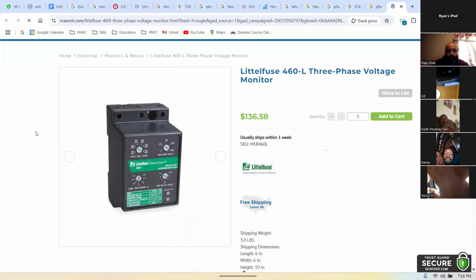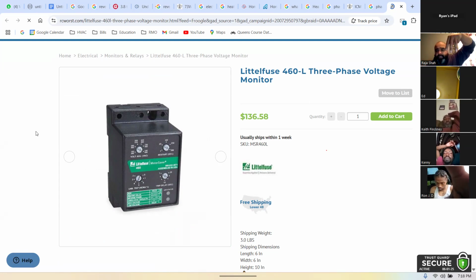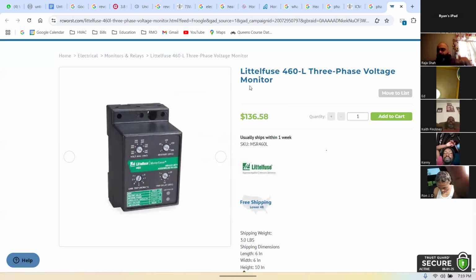All a phase monitor is, Ryan, this applies to you too when you're doing electrical: when the three legs are coming in, remember we're dealing with three phase, three phase 208. So you're talking about 120, 120, 120 on each leg. If one of my 120s goes too low, let's say it goes to 90 volts.